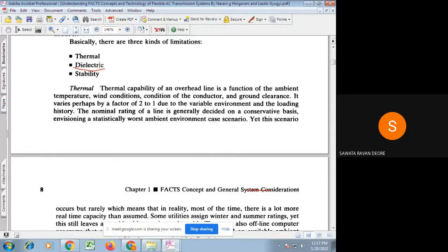Obviously there is some protection against such conditions, like, in order to avoid over voltage, protection against over voltage, we use some arresters, that is metal oxide arrester or some surge diverters that you already studied in switchgear and protection. So that is the second factor which limits the loading of the transmission line.